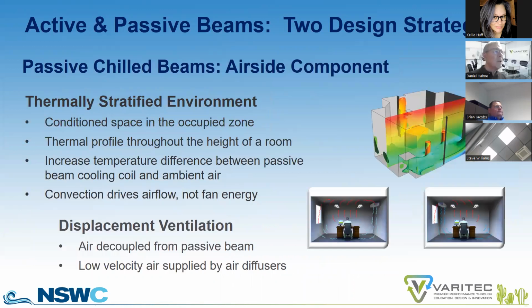in a thermally stratified environment, because of the forces of convection. If a beam is placed locally over the top of a sedentary occupant, it could actually cause thermal comfort issues, overcool the occupant, and create a sense of discomfort. An excellent place in Phoenix, where we have high temperature perimeter walls, is to place that passive chill beam over the perimeter wall, so the heat in the convective plume off the warmer wall to the space temperature is actually dealt with at the chill beam, and that cool air is then redelivered to the space via convection. Fan energy is not required.